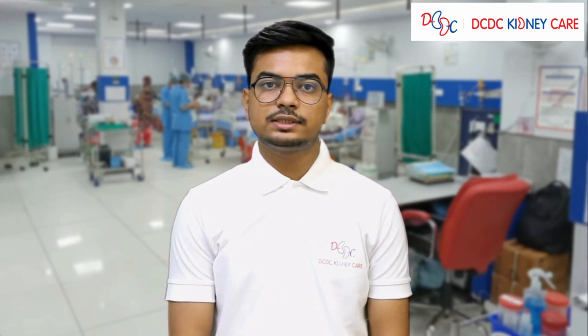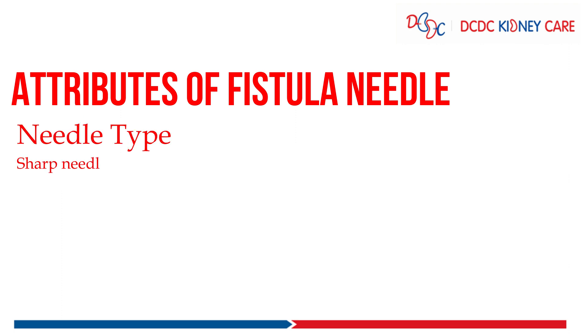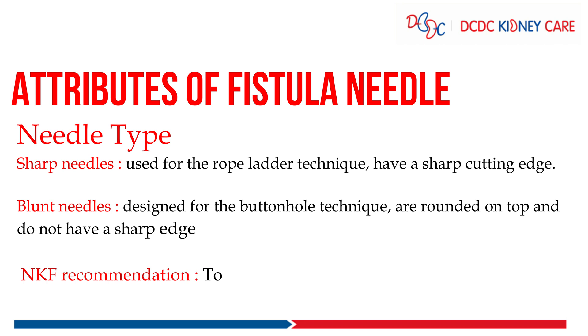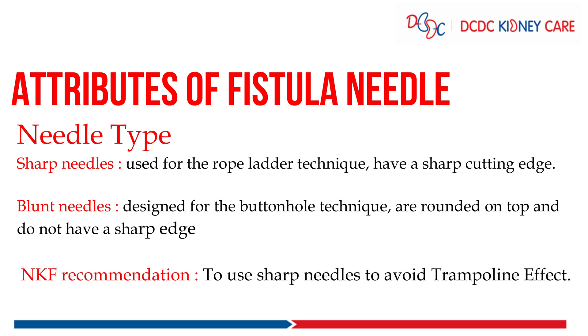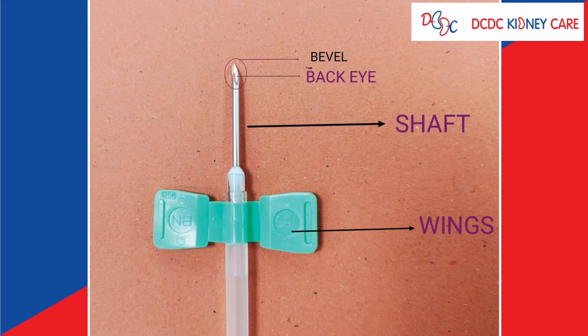Firstly, we will discuss the attributes of fistula needle. The first attribute is the needle type. Generally, we have two types of needles: one having sharp edges called a sharp needle, and the other having round edges called a blunt needle. We generally use sharp needles as per the National Kidney Foundation's guidelines. The fistula needle consists of wings, needle shaft, bevel, and back eye.